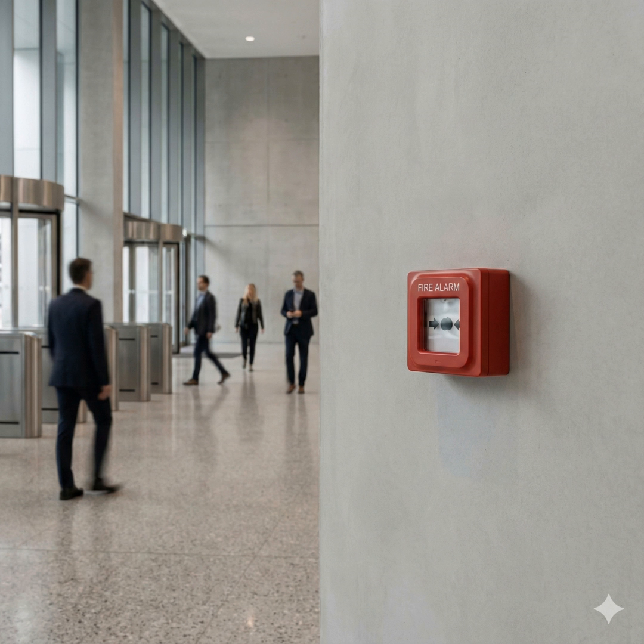Okay, so let's unpack that core architecture layer by layer. Our sources consistently define the fire alarm system as this coordinated network, and it's built on three functional layers that have to work together. You've got the sensors, the control panels, and the notification devices, and they're all constantly monitoring the environment for signs of fire and processing that data immediately. Exactly. While the sensor layer is providing the input, the control panel's role is really the central processing unit. It's the decision maker for the building's safety response.